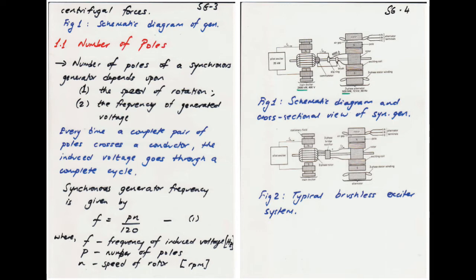And the armature is connected via three-phase windings, okay, and it's connected to your slip rings, which are mounted on the shaft, and thereby it will pass through and go onto your load. So with this first type, which is stationary field, the problem with these machines is they require a set of brushes sliding on slip rings, enabling the armature to be connected to the external load. And the problem is that it requires high maintenance, because those brushes are subjected to wear and tear.